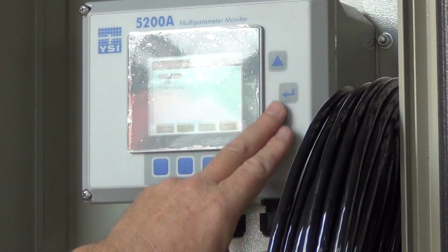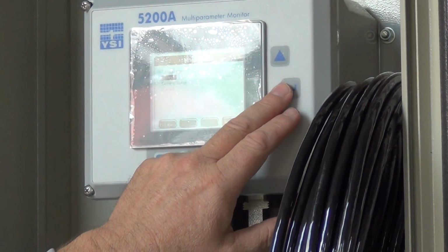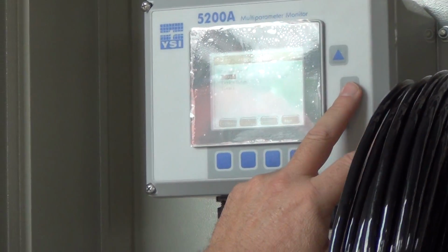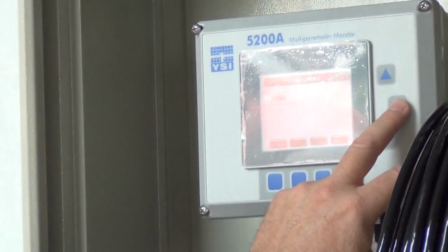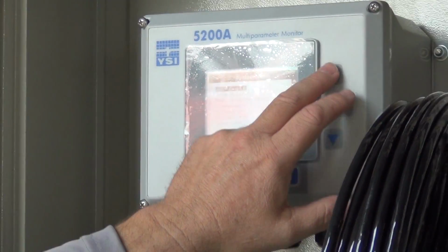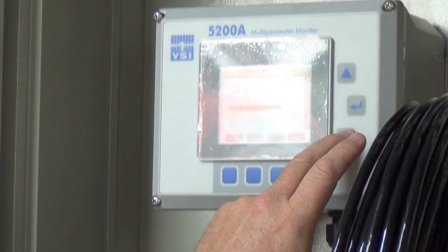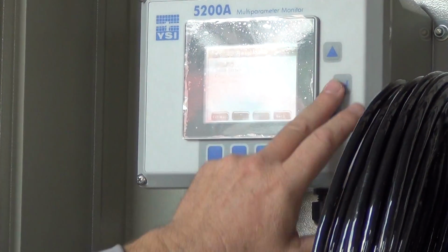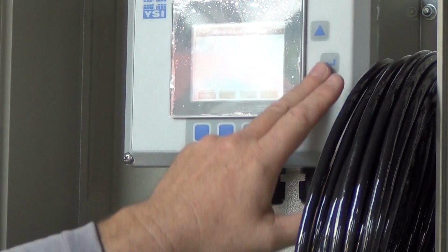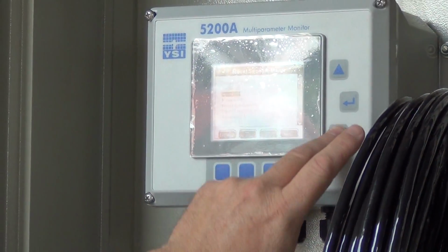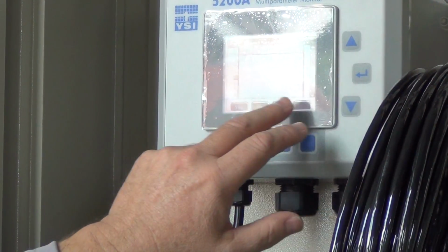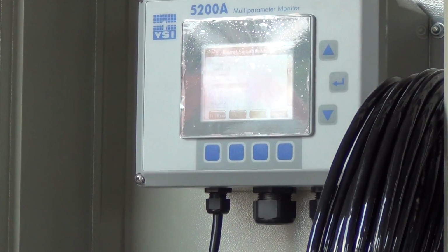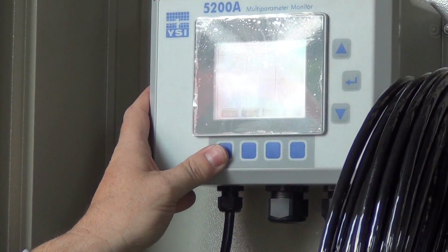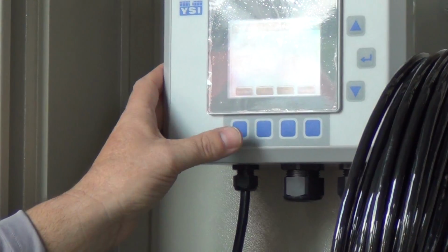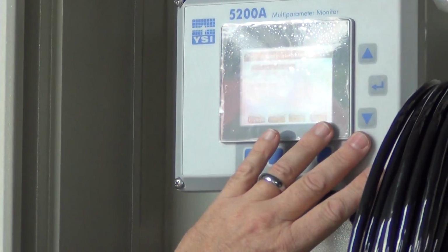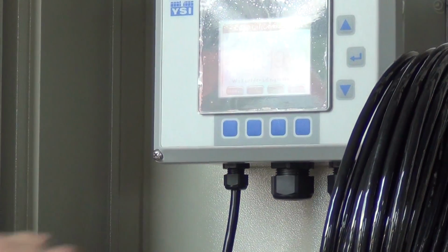And I'm going to reset the probe because the first time we do it, sometimes you have to. Remember where I said factory reset? Be careful. So I'm going to go System, Service, Reset to Factory, Reset Sensor, Reset Conductivity. Are you sure? Yes. I'm going to exit, Menu, Calibration, Conductivity, and wait.